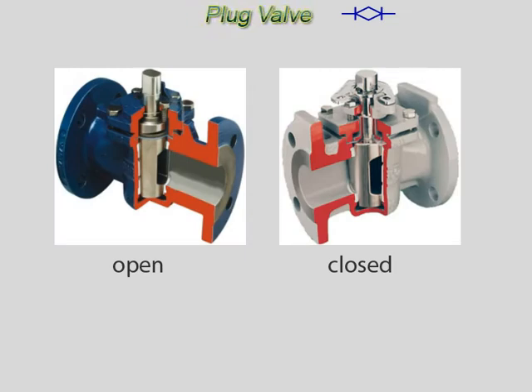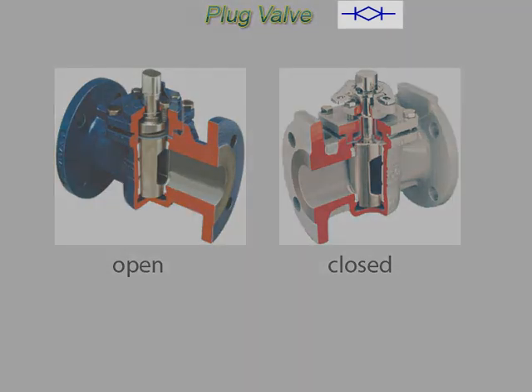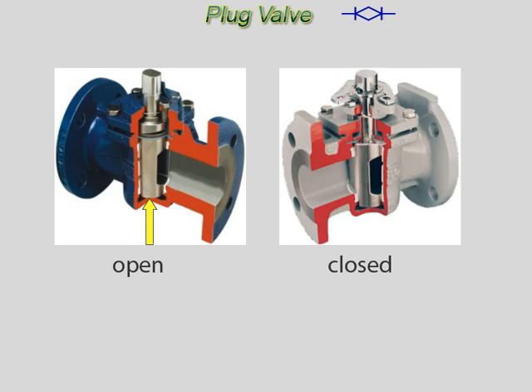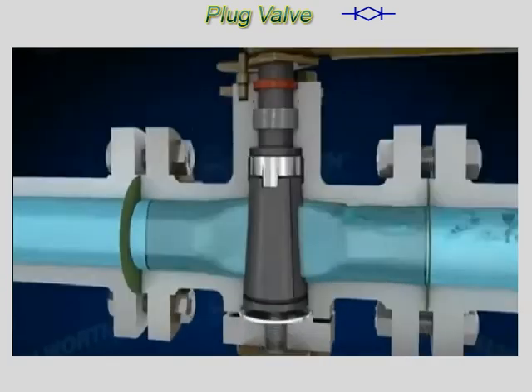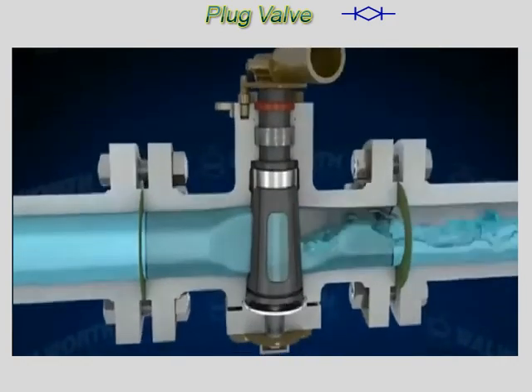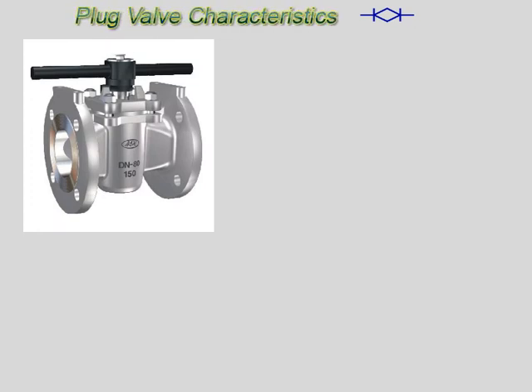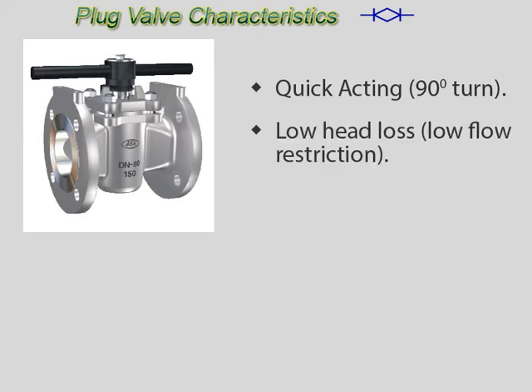A plug valve is another rotational motion valve used to stop or start fluid flow, similar in operation to a ball valve. The name plug is derived from the shape of the disc, which resembles a plug. In the open position, the passage in the plug lines up with the inlet and outlet ports of the valve body. When the plug is turned 90 degrees from the open position, the solid part of the plug blocks the ports and stops fluid flow. The main advantages are quick-acting quarter-turn on-off operation, very little flow restriction when open, and positive flow isolation with low torque. The main disadvantage is poor throttling characteristics. Plug valves are usually relatively small in size, approximately 6 inches in diameter or less.